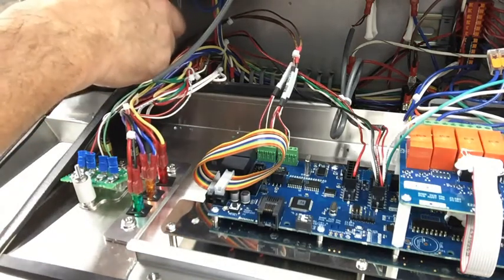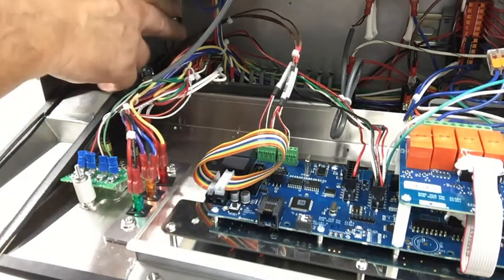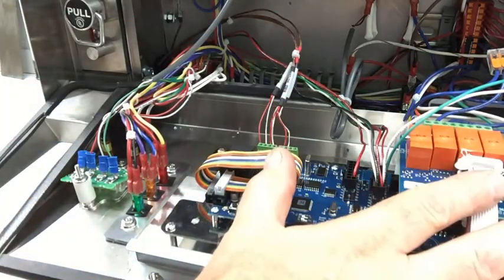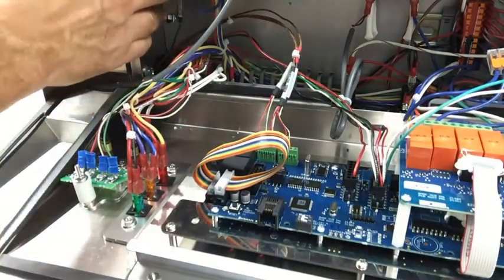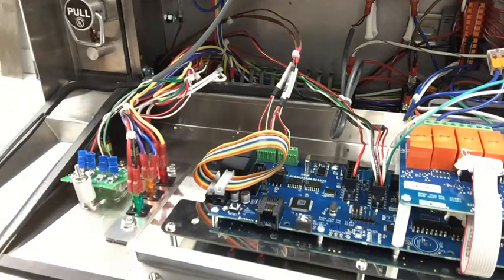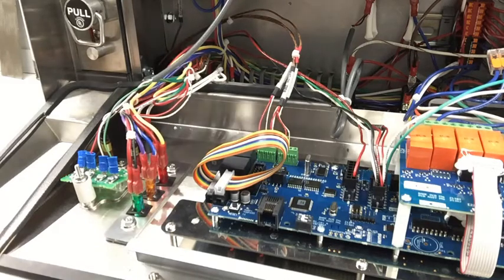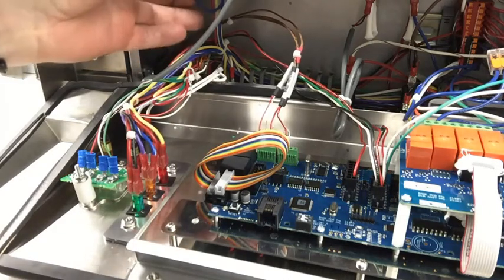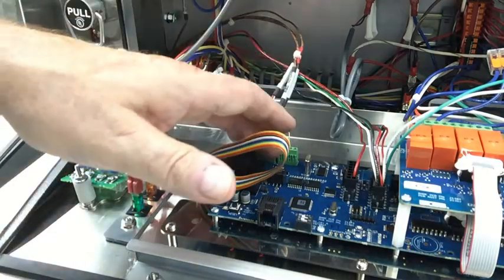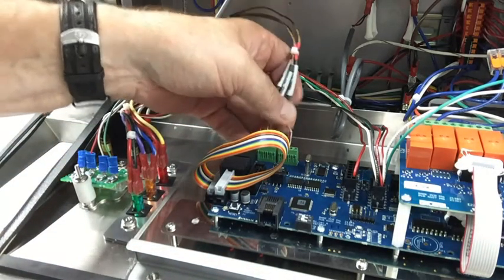It goes to this high limit module alone. Again, separate in case something goes crazy or wonky with the controller. It'll go ahead and catch it on its own and shut it down if it hits 450 degrees. It's an additional safety, one that's actually mandated by UL. So it is separated from the others. All the other 3 go to the controller.